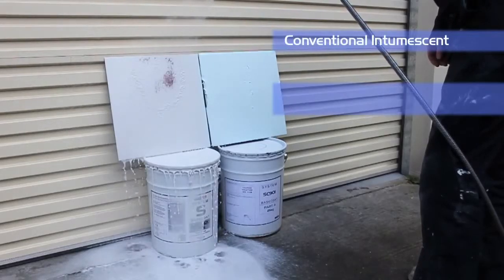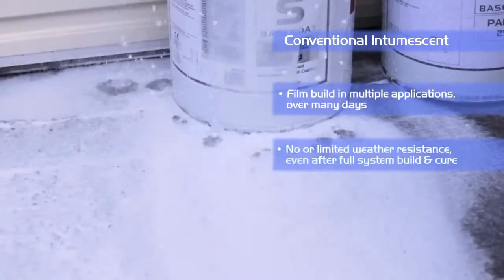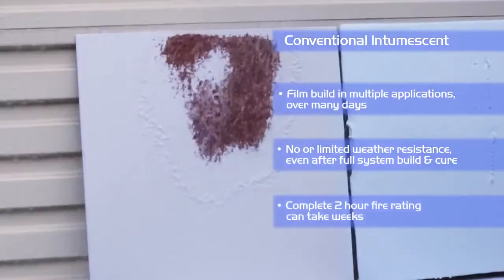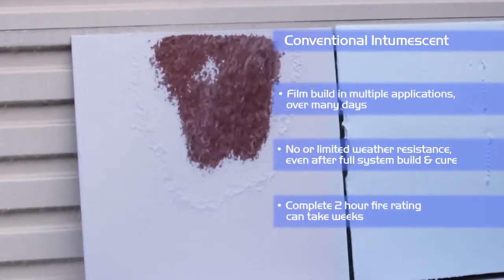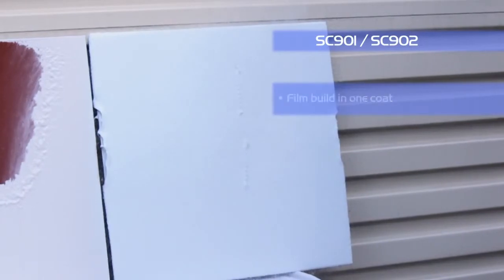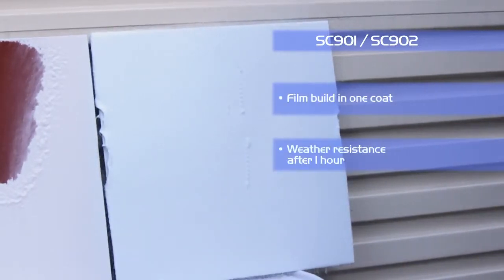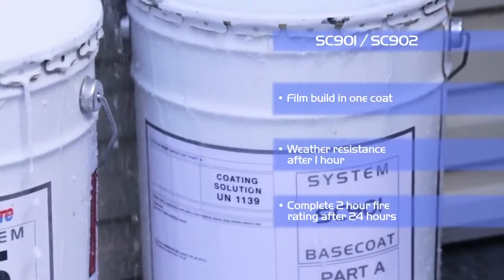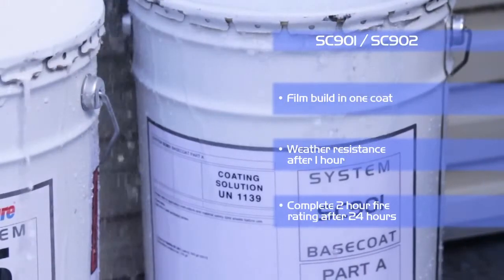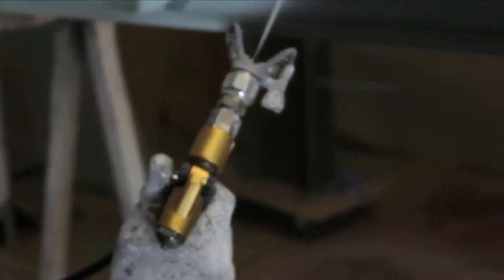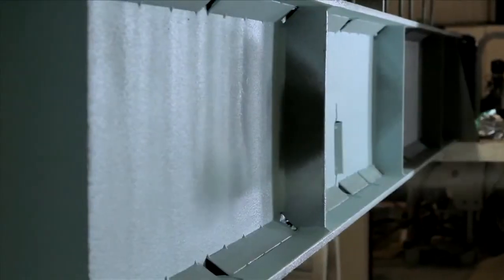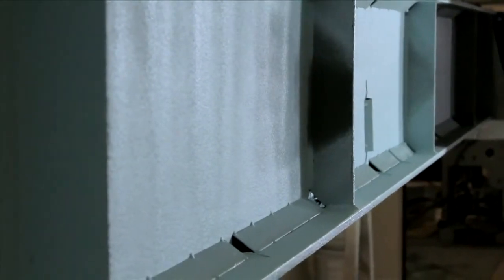Conventional intumescence have limited resistance to environmental conditions during the construction phase and can be easily washed off. The off-site SC901 system is touch dry, weather resistant and over-coatable within 60 minutes. Where required a top seal can be applied the same day and can be transported within 8 hours of coating. The on-site SC902 system is also touch dry and weather resistant within 60 minutes with the top seal being able to be applied the following day.